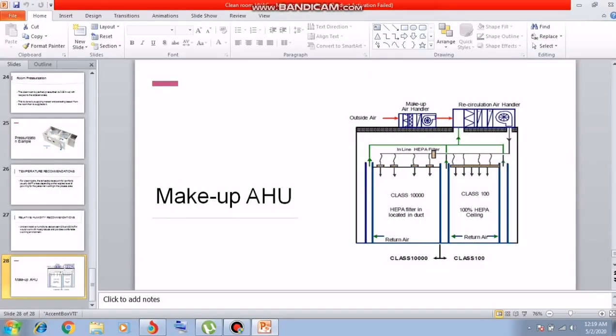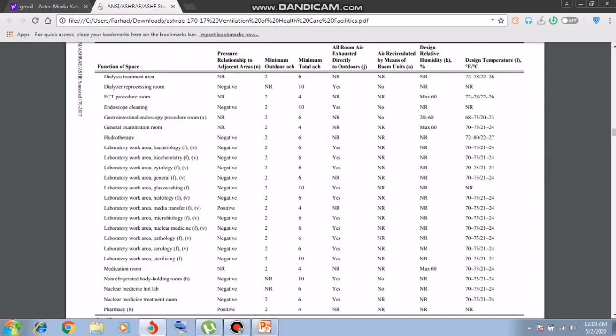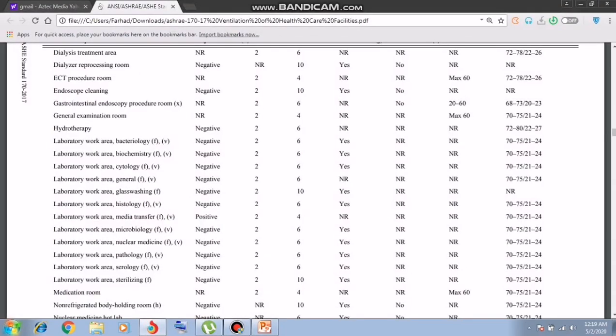How will we recognize what kind of filter we need? So you just need ASHRAE 170, that is the code 170 for this. Like you can see, just zoom in, the laboratory work area bacteriology and laboratory work area biochemistry.